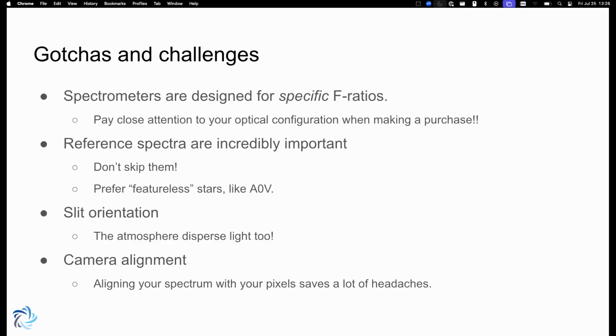A lot of the software nowadays, and a lot of the instructions for how to use the software, allow you to skip this technique because you have to go out and collect a spectrum. This is going to be like 10 to 15 minutes a time, and then you have to go look at your science object. That's 10 to 15 minutes a time, and then you go back to your reference spectrum. So you spend like 30 minutes collecting calibration data and 15 minutes only collecting the science data. However, in a lot of cases, collecting the calibration data is really important because it allows you to find small flexures in your system and get much better calibration out of it than what you would otherwise.